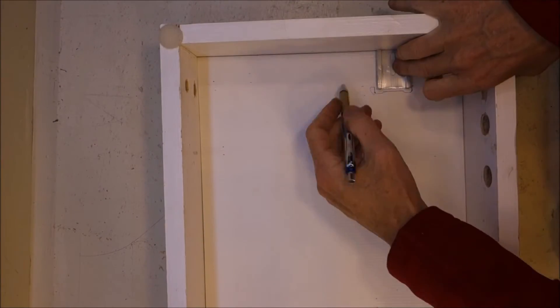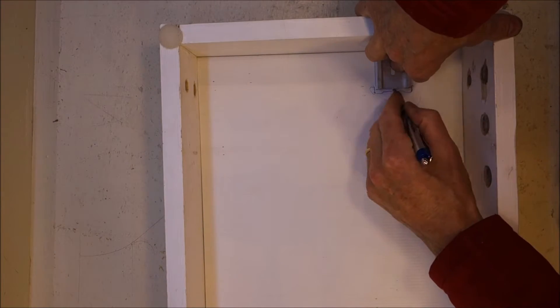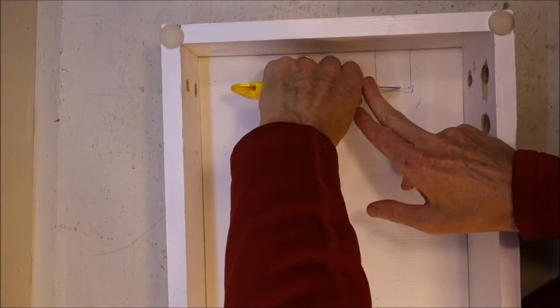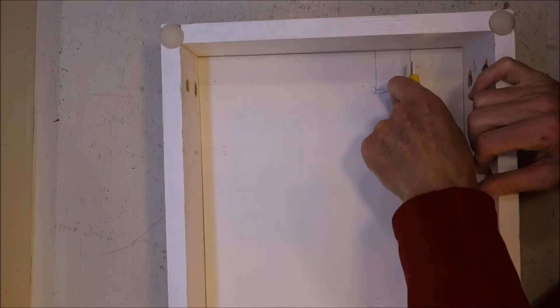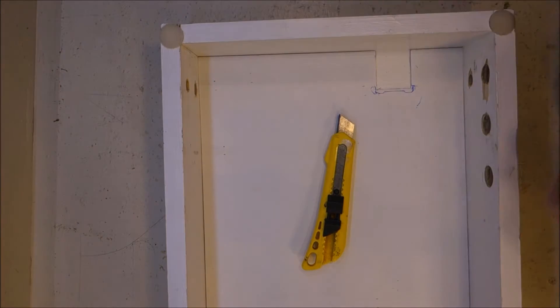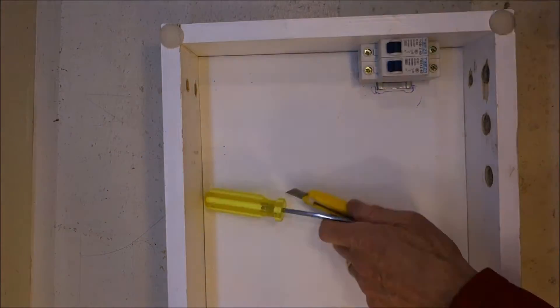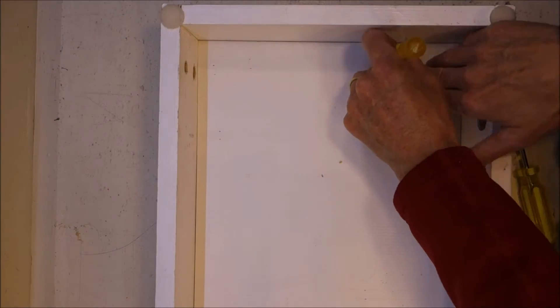The breaker switches are what are known as DIN rail mount switches, so they clip onto a strip of metal which I've cut short, and I'm screwing the piece of metal into the back of the box, which means I can replace or pull out the breaker switches nice and easily using the DIN rail system.